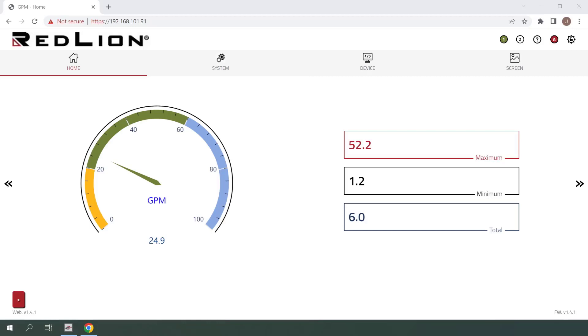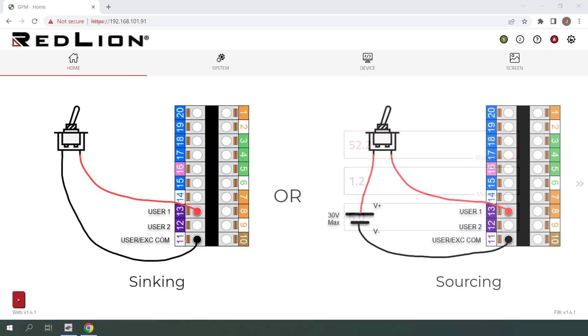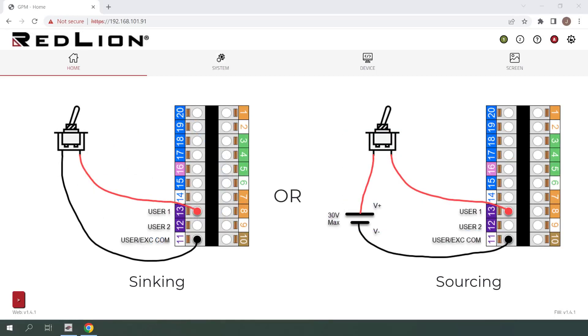Before we get started with configuration, we'll take a quick look at how the user inputs are wired, with user input 1 as an example. As you can see, it's possible to wire the user inputs using either sinking logic or sourcing logic. The key difference being that sinking logic does not require any external voltage to be applied and sourcing logic does. You'll see here that the same terminals will be used either way.